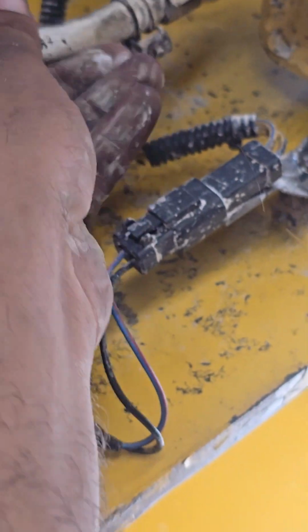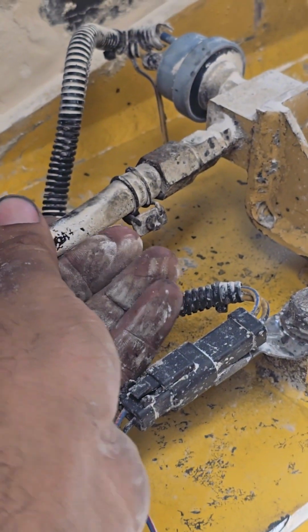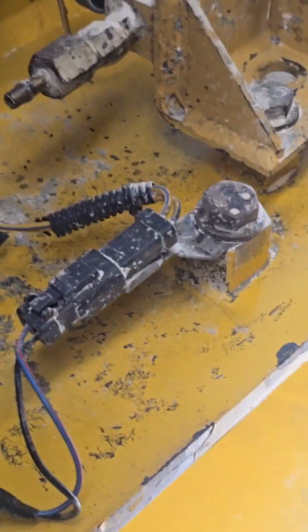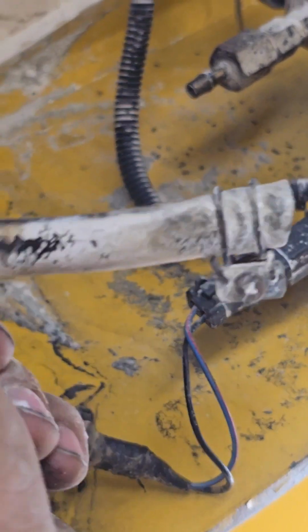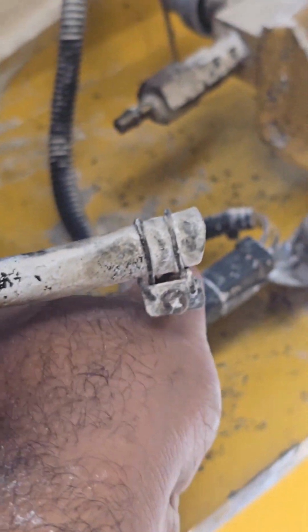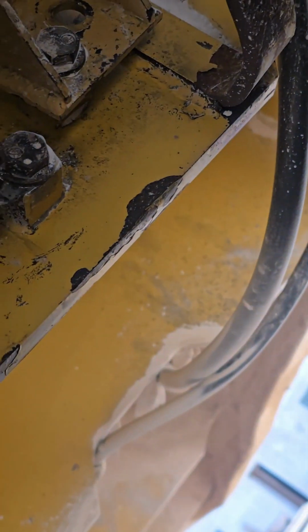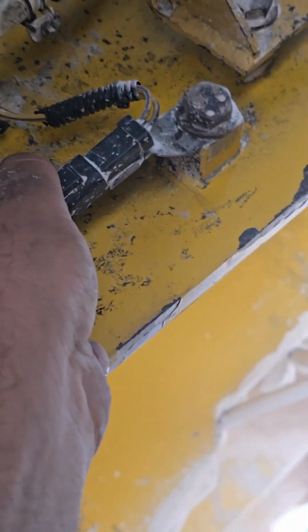Now we physically check the hole. This one does not have any dust. We see the hole, but there is no dust. In some cases the filter is dustier, dust gets inside, and the sensor does not vacuum properly.